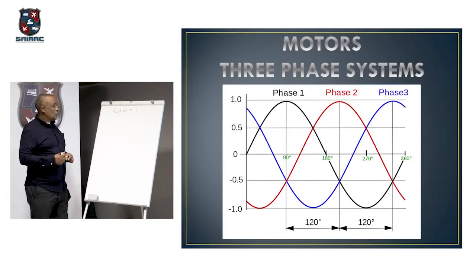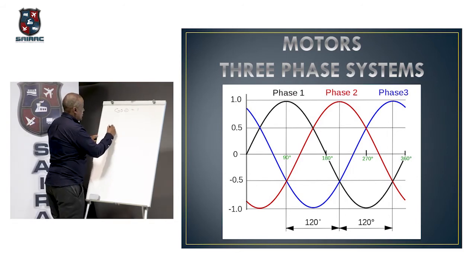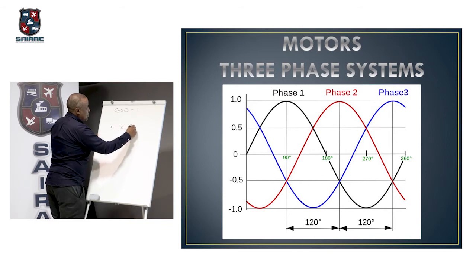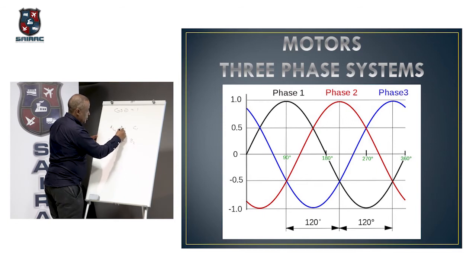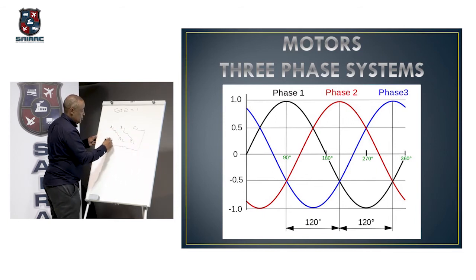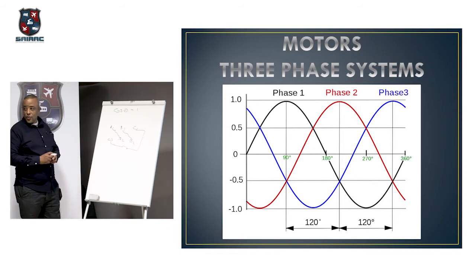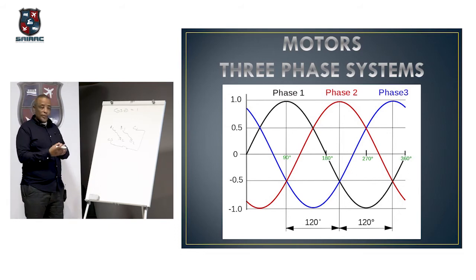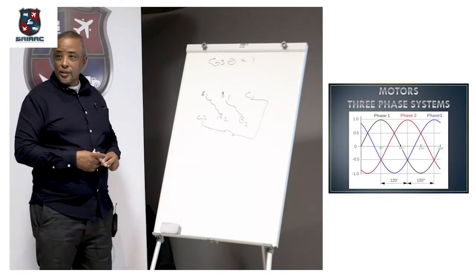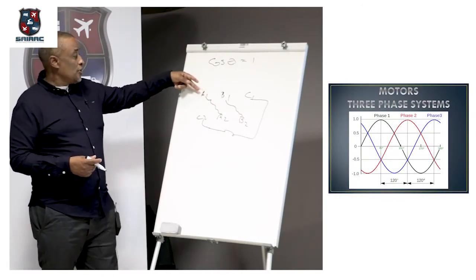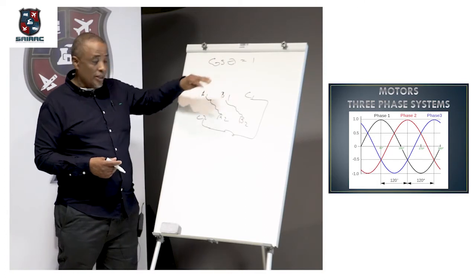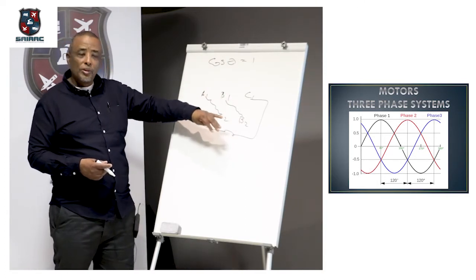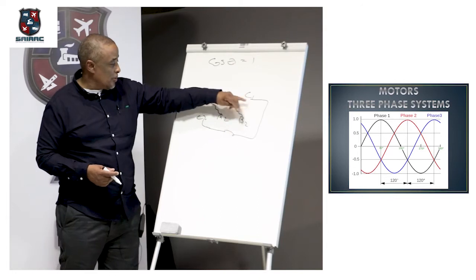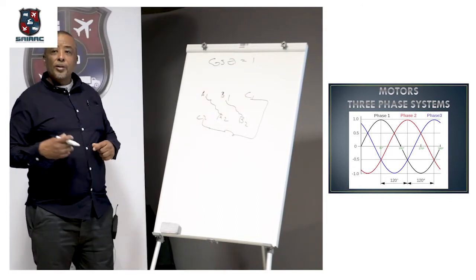Okay. Motors can either be connected in star or delta. A1, B1, C1, C2, A2, B2. Okay, those are your windings of your motor. 3 sets of windings. Okay, the beginning of the windings we call A1, B1, C1, and the ends we call C2, A2, B2. A1, A2, B1, B2, C1, C2. Happy with that? Okay, we have a choice.